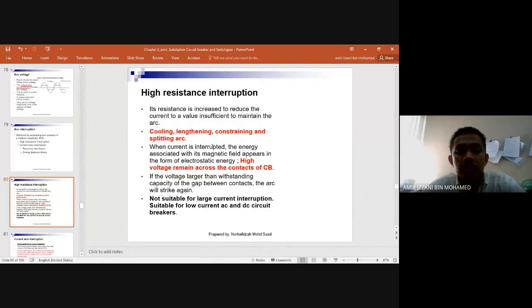Okay, when current is interrupted, the energy associated with its magnetic field appears in the form of electrostatic energy. High voltage remains across the contacts of the circuit breaker. If the voltage is larger than the withstanding capacity of the gap between the contacts, the arc will strike again. Okay, if the voltage is high enough, arcing will strike again. We will discuss further in the high voltage section why high voltage will restrike the arc, will reproduce the arc. This is not suitable for large current interruption, suitable for low current AC and DC circuit breakers.